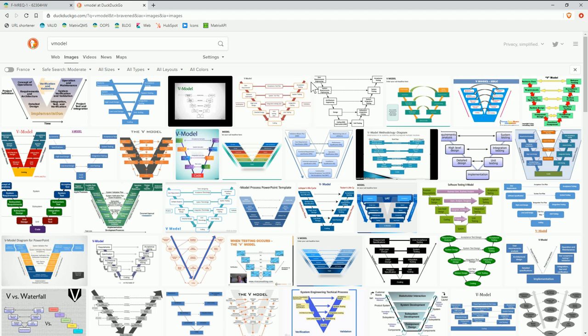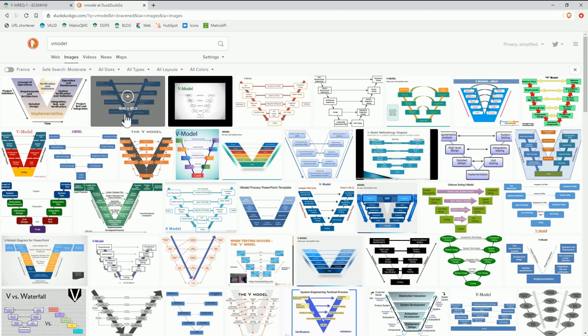The idea of a V-model is that you have on the top left the market or user requirements. And then as you proceed in your project, you go down and you have finer and finer requirements — system requirements and then at some point maybe software requirements. And once that is done, you do the implementation. And then you need to go up on the right-hand side to actually verify or prove that the different layers of your design work correctly.